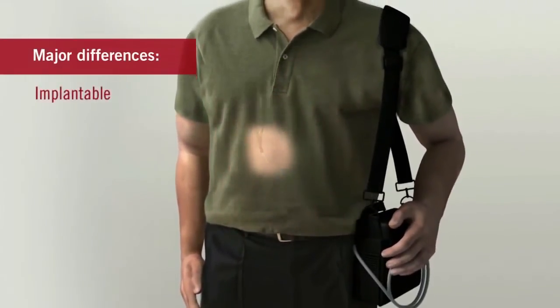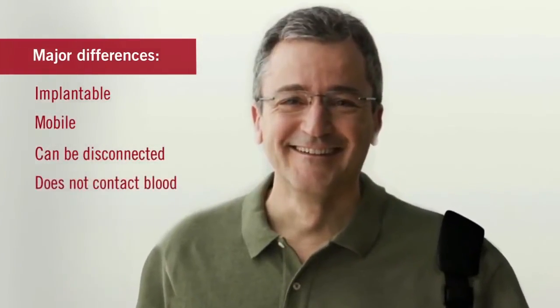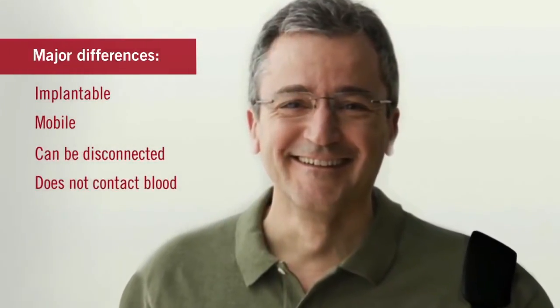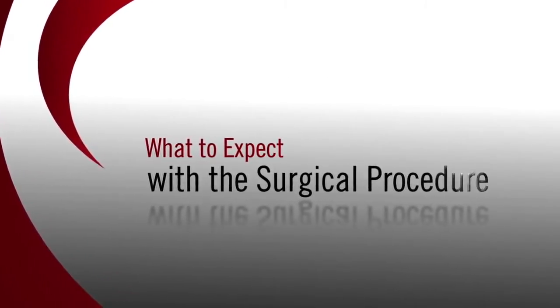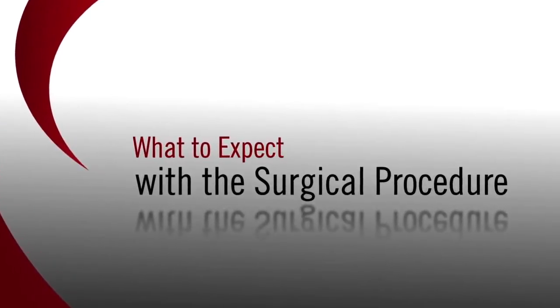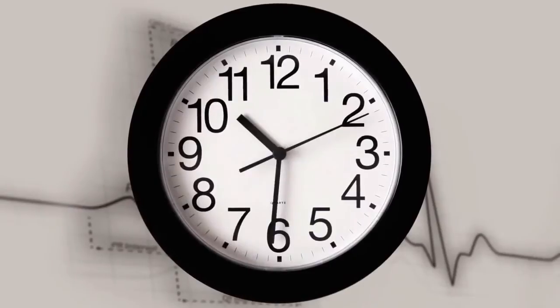A major difference is that it is implantable, mobile, can be disconnected, and does not come into contact with blood. The driver is worn externally and is portable. The C-Pulse Heart Assist Device may be implanted into the patient in about two hours.